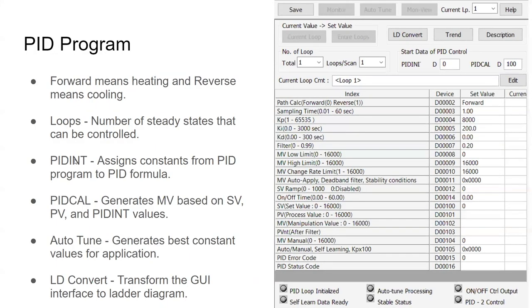To recap: PIDINT — PID initialization — is used to assign the constants from the PID program to the PID formula. Those constants consist of the sampling time, KP, KI, KD, and filter. These are all constants except the SV, PV, and MV. PIDINT loads those constants into the formula and shouldn't be changed throughout the whole application — not to say you can't, but maybe that shouldn't be the first time you do it. Once you gain more experience and exposure to PID, you can start changing the constants at will.